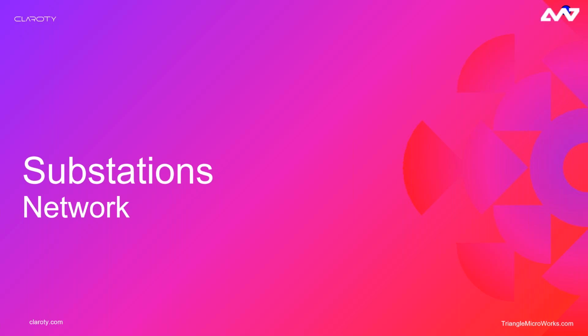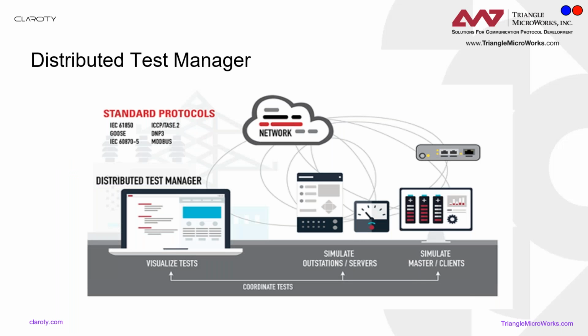So let's talk about very basic substation networks. What we can do is we have Distributed Test Manager, which is our substation network simulation tool, and we'll be presenting that today. It allows for protocol devices, including 60870-5-101 and 104, ICCP or TASE.2, DNP3, Modbus, and IEC 61850 devices to be simulated. DTM will be used to simulate the substation that Claroty will be monitoring.